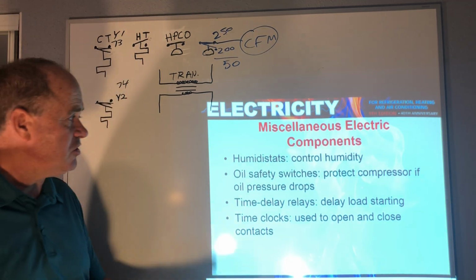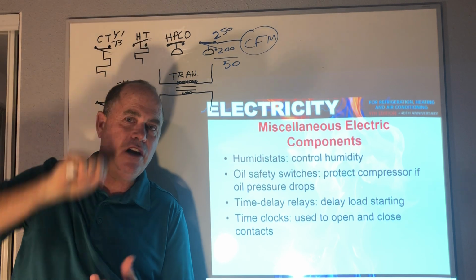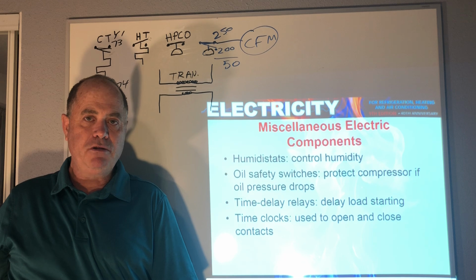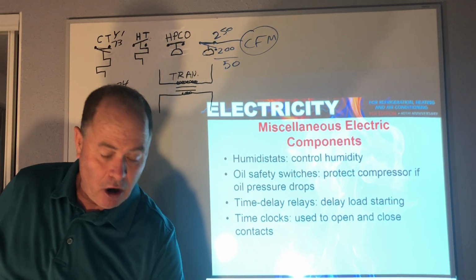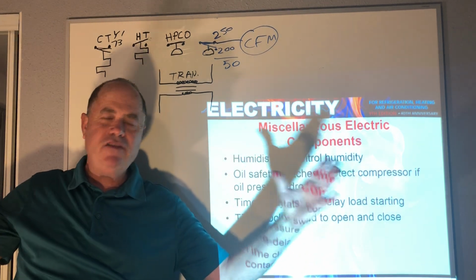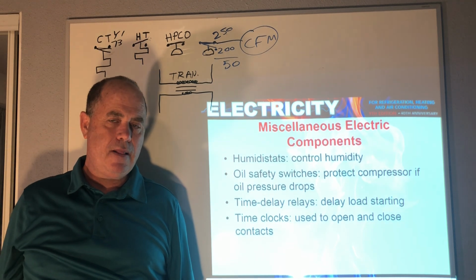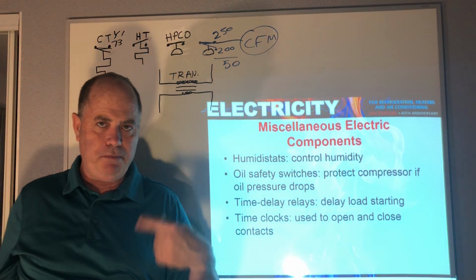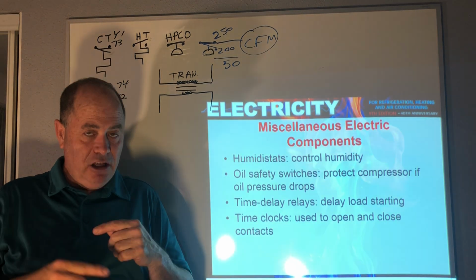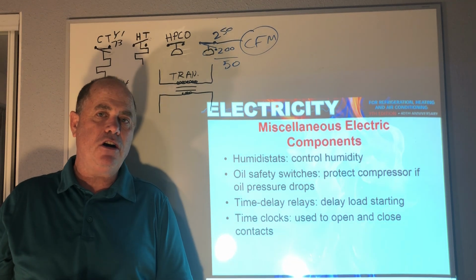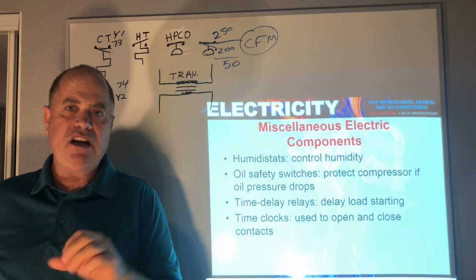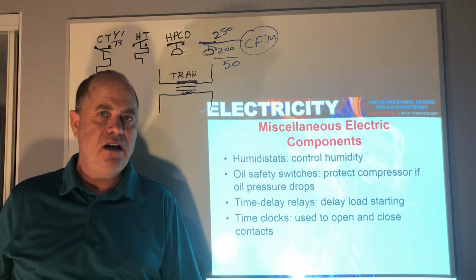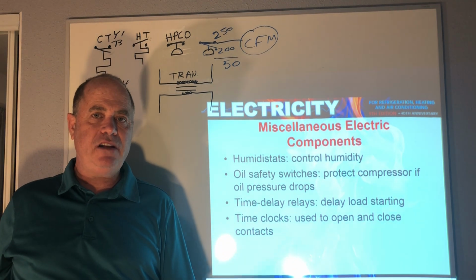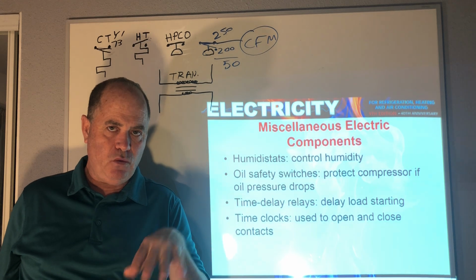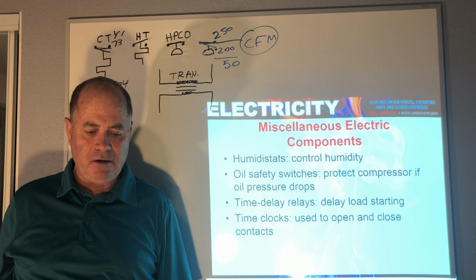Oil safety. All small compressors like this big and smaller work on the splash method of lubrication, with oil inside the hermetically sealed compressors. All really big compressors have a separate oil pump and usually an oil heater that feeds it before it starts. The mid-sized compressors like semi-hermetics sometimes have built-in oil pumps that, when the compressor turns, lubricate the internal parts. Since it's lubricating itself, it'll give it 90 seconds to establish good oil pressure. If it doesn't, it says something's wrong and shuts the system off. Usually there's a manual reset button that a technician has to hit while troubleshooting in order to restart the system.